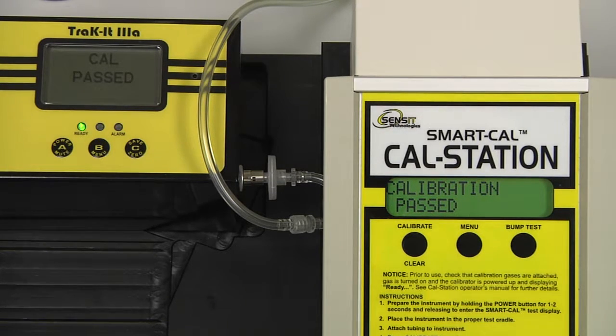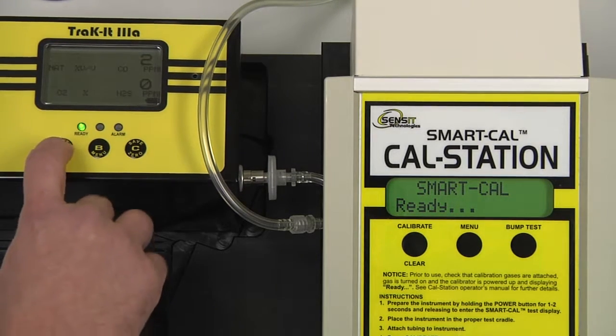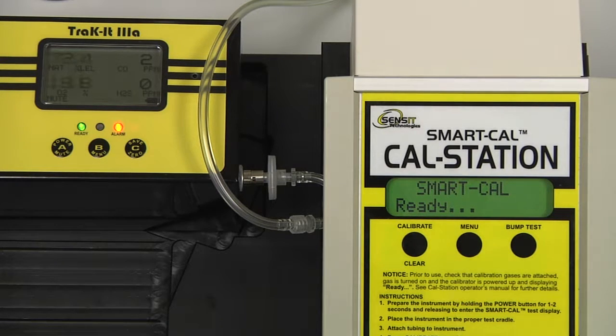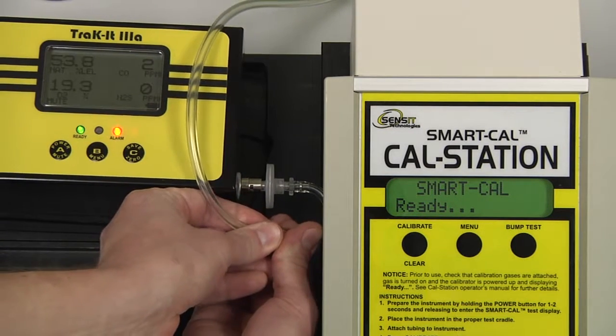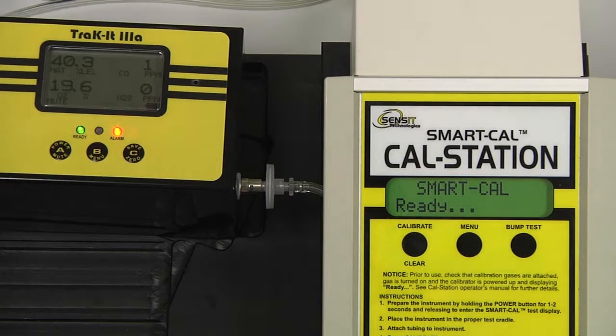Calibration is passed. We can exit out of the calibration mode on the cal station by pressing and releasing the clear button. And the instrument will be returned to the working display. We can now disconnect our instrument hose and allow the instrument to purge before powering off.